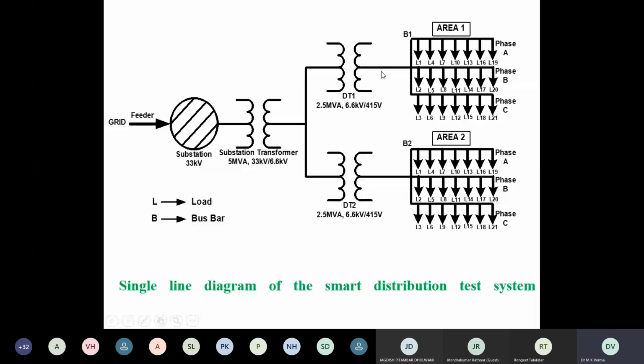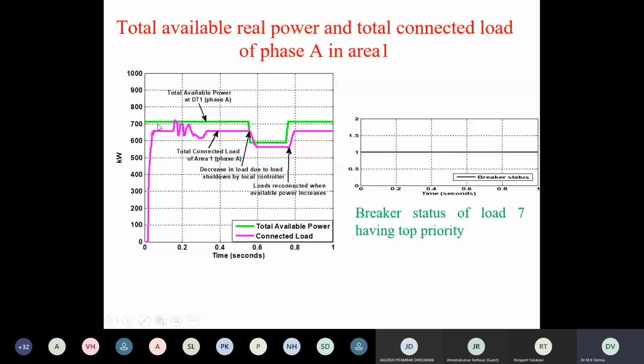Now, these are different plots. This is the total available power at the substation, and this is the plot of kilowatt consumption of area 1, total kilowatt consumption. So you see at this time the available power has gone down. Since available power has gone down, this has been detected by the master controller, and then some loads are disconnected. Some of the loads are disconnected.